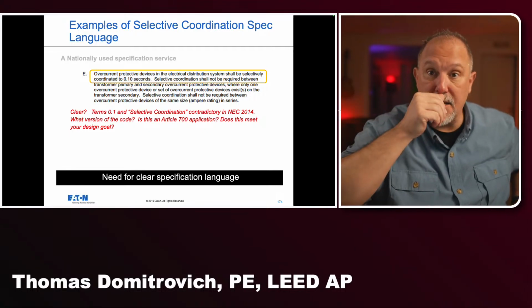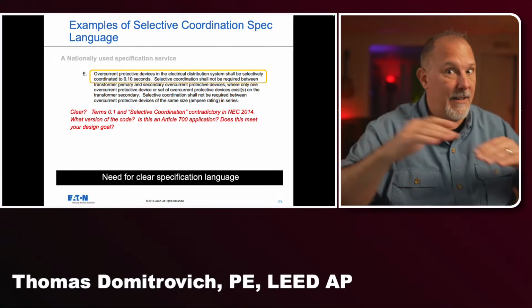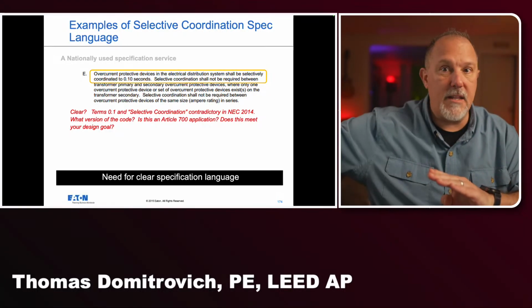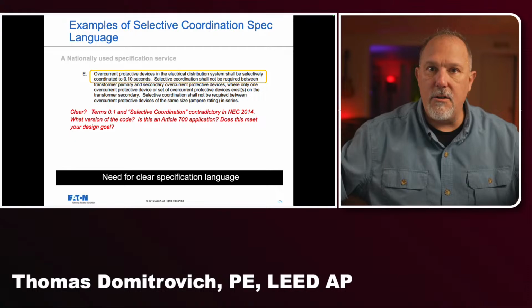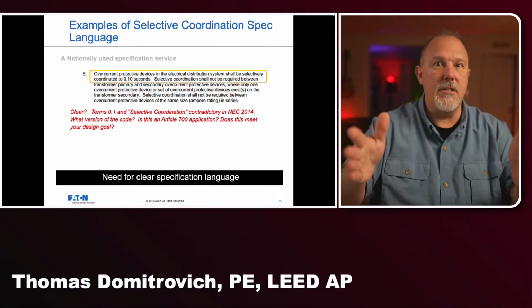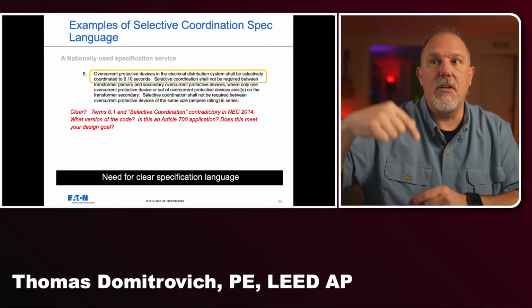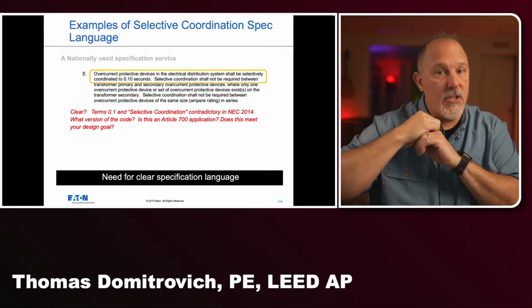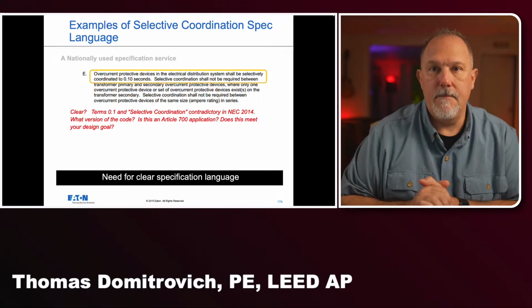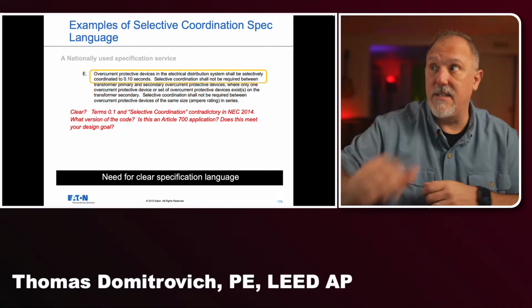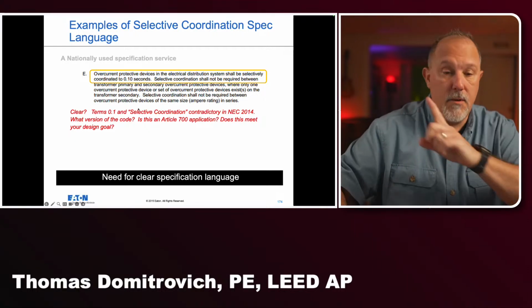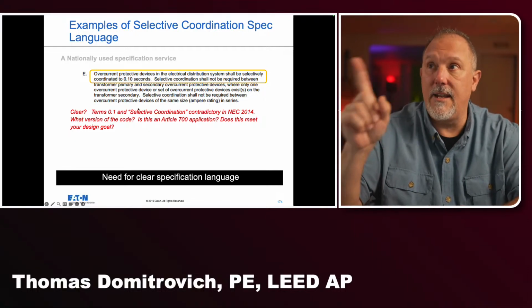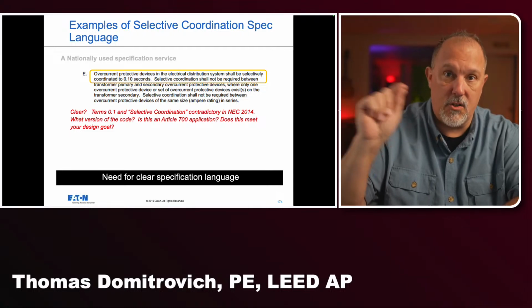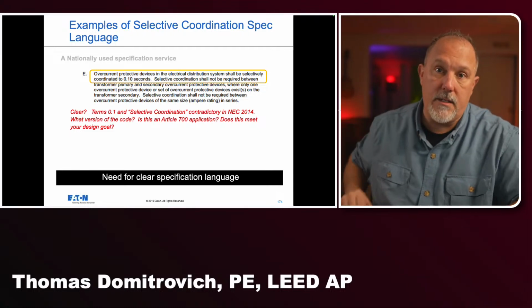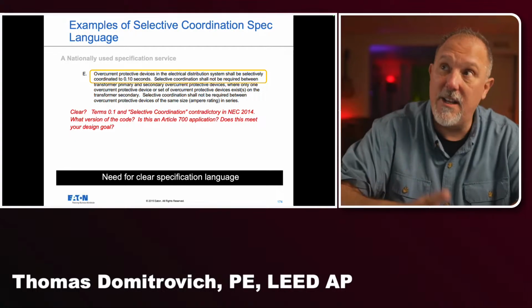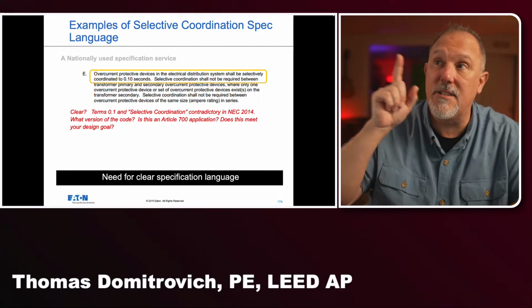All we did was look at the trip curves down to 0.1 seconds. I maintain separation, forget about the available fault current, hide the overlap down below. I'm good to go. If you have to selectively coordinate that system, you're going to have to change your design probably. That's going to be a very expensive fix. So I can guarantee that if I was given this to quote, I would not be quoting selective coordination. And then you know who pays for it? The design engineer, because of the spec.